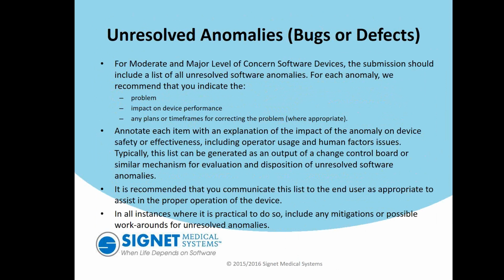Most companies have the concept that if it is a high-level bug, like we call it a P1 bug, or companies sometimes have different levels, but a crash bug or a bug that causes a serious amount of harm, the software review board that you set up, which should include your development organization and your quality organization as well as clinical, will decide that we can't send this product out with this particular bug. It's too much. We're going to respin it, retest it.